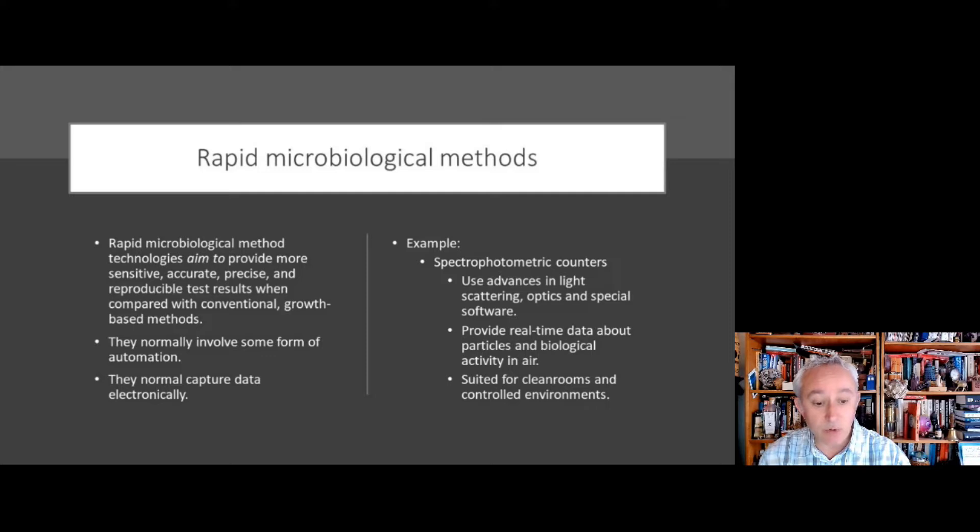So they have a reasonable chance of picking up most things that could be microbial. The downside is that they can sometimes fluoresce to non-biological events. So if you spray glove wash too close to these, or sometimes clothing fibers can also simulate the same response.